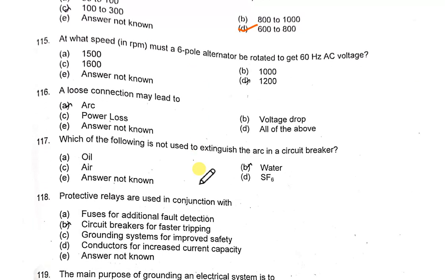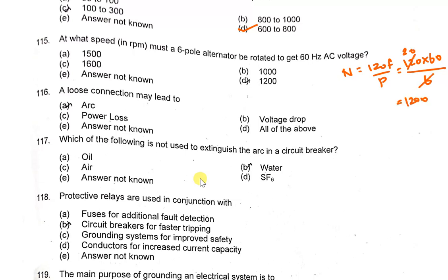At what speed must a 6-pole alternator rotate to generate 60 Hz AC voltage? Using N = 120F / P, with frequency 60 Hz and 6 poles, the alternator must rotate at 1200 rpm.